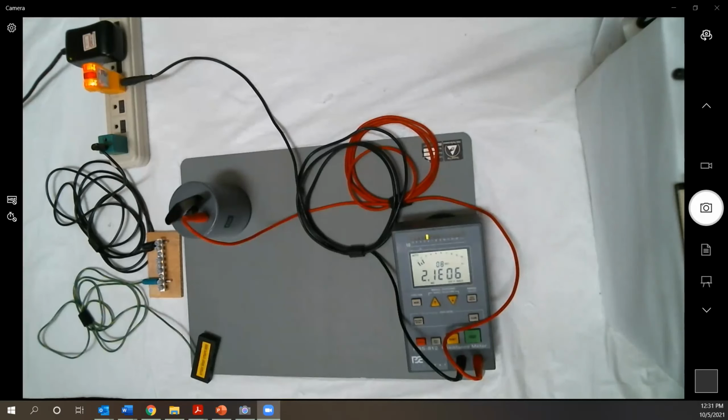And Gary, from what I understand, there were some materials, I'm not sure we have them anymore, but if they were tested at a higher voltage and they were quite conductive, it might actually damage the materials, burn little pathways through the material, so you wouldn't be getting a true reading. And so that's another reason to start low until you know what you're measuring. All right, thank you.